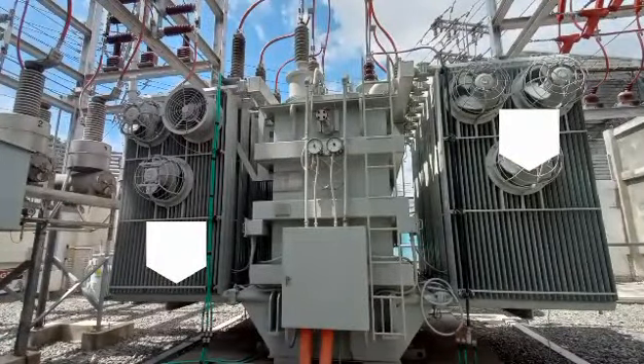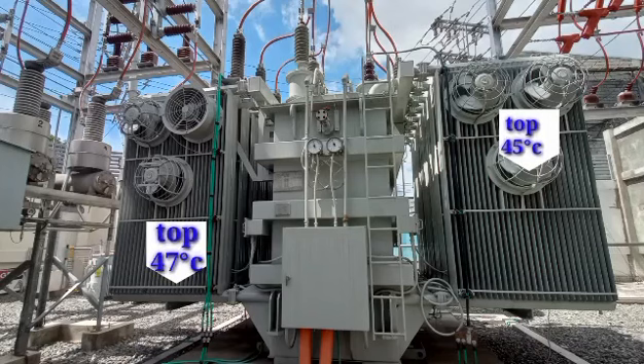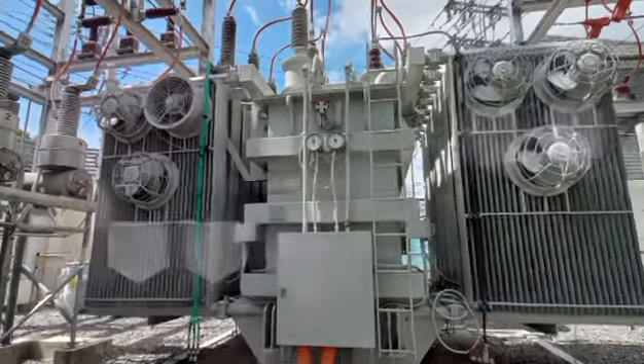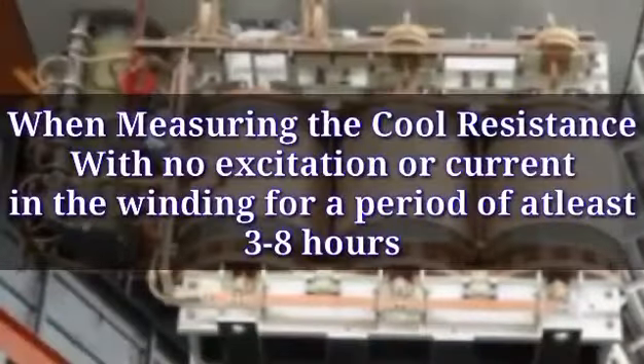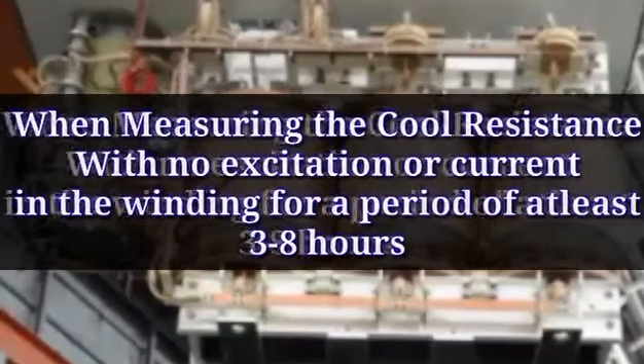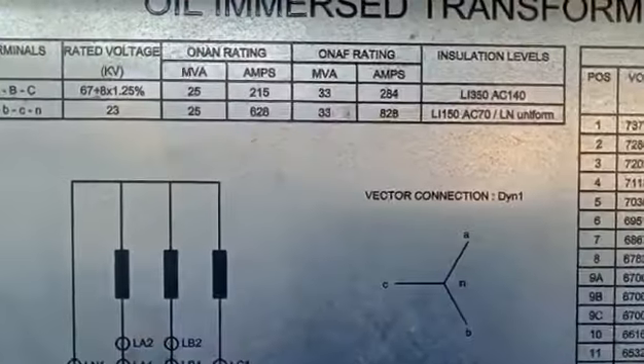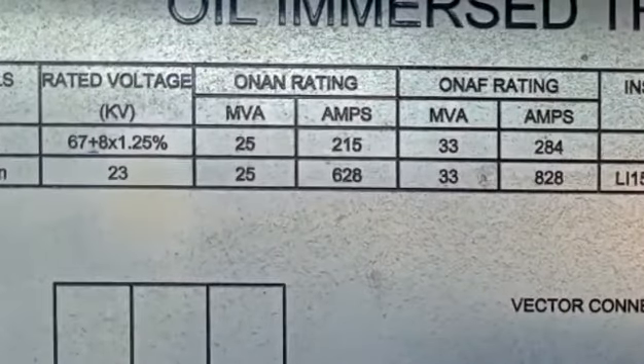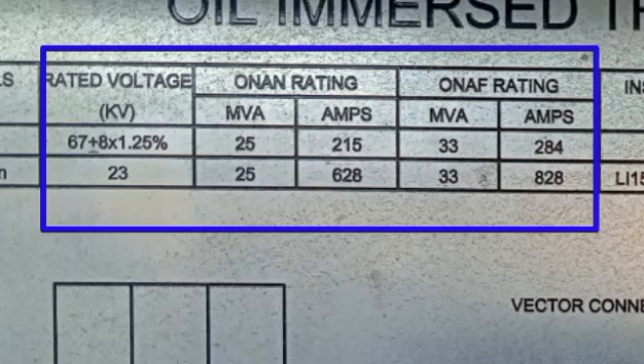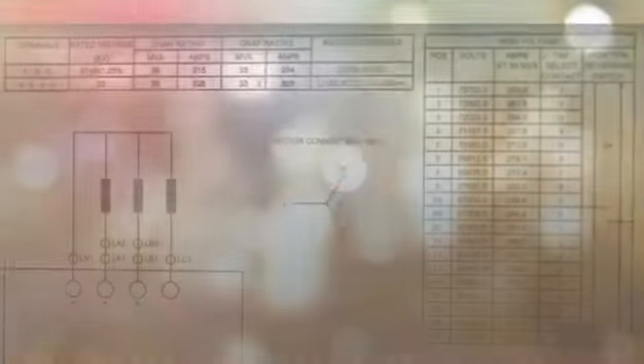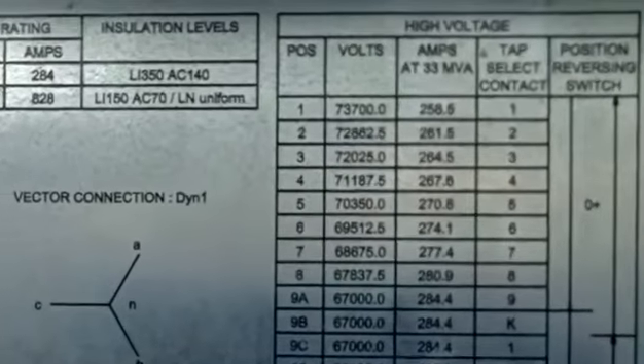As a piece of additional information, the temperature differential between the top and bottom oil temperatures shall be measured with thermometers, and shall not exceed a 5 degrees Celsius difference. The winding shall be under the insulating oil with no excitation or current in the winding for a period of at least 3 to 8 hours before the cold resistance is measured. Now looking at the sample test, a 3-phase, 33 MVA power transformer, 60 Hz, having 67 kV to 23 kV secondary. The winding resistance is measured as shown, in each tap position and in every phase of the primary winding.